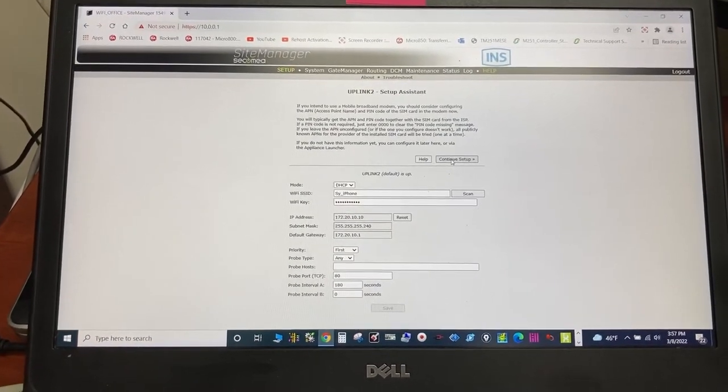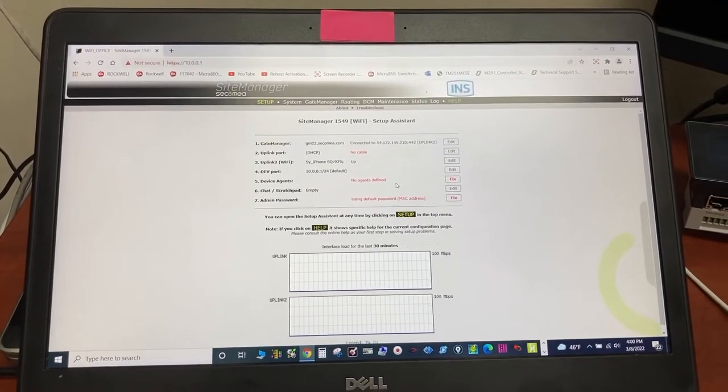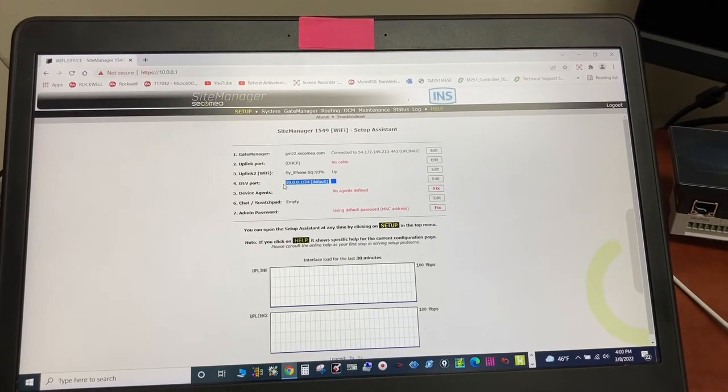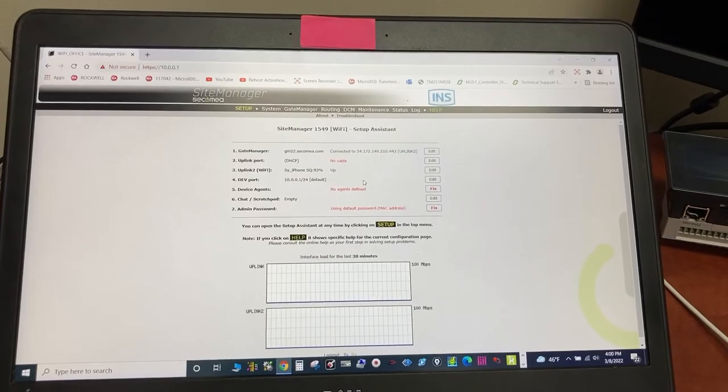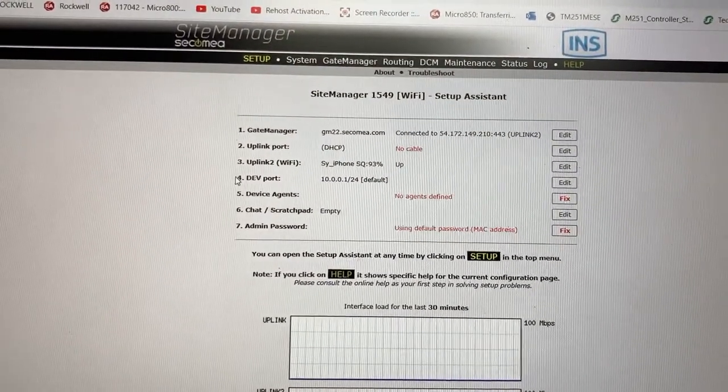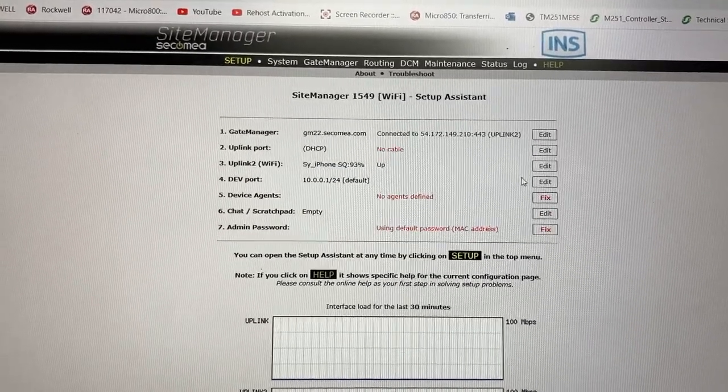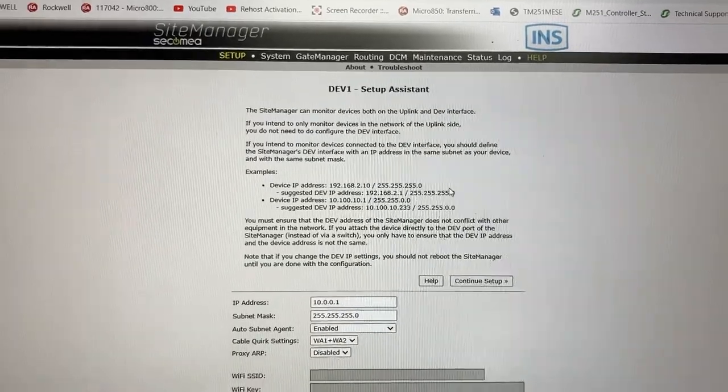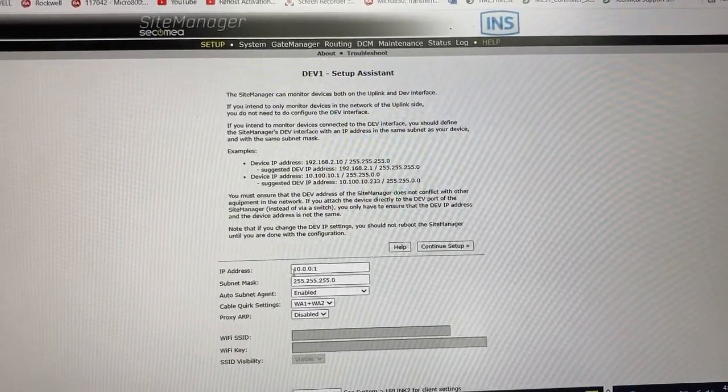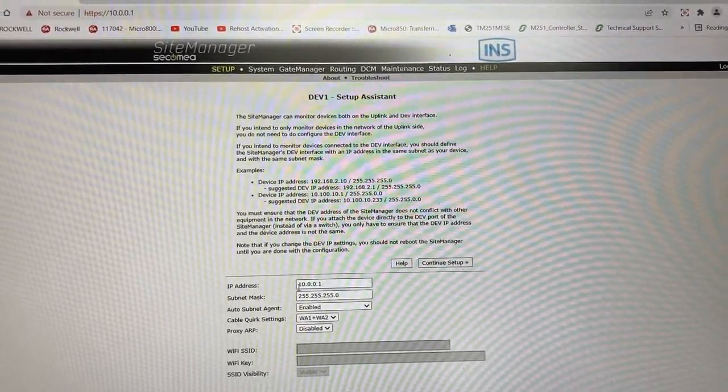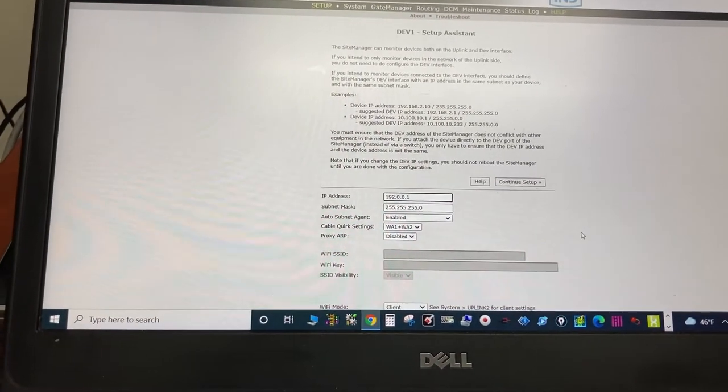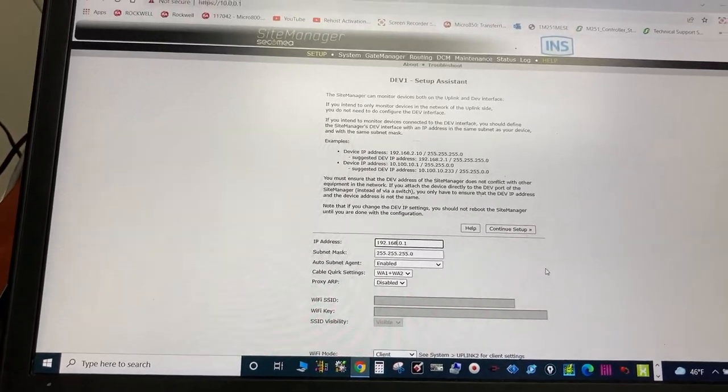Continue setup. We also need to change the IP address here to make the gateway on the same network with the PLC. Go to devport, edit. The PLC IP address is 192.168.0.90 so this will need to be 192.168.0.1.